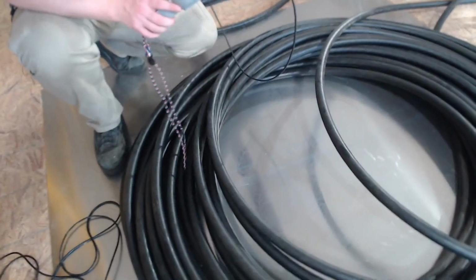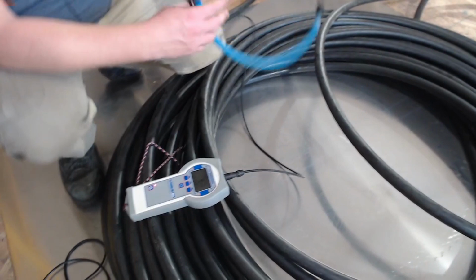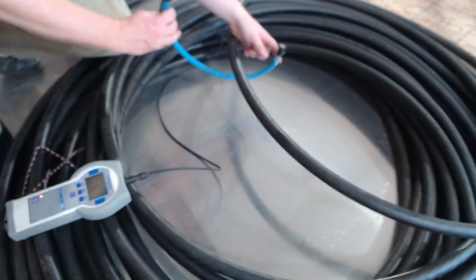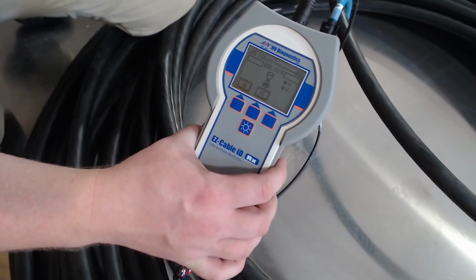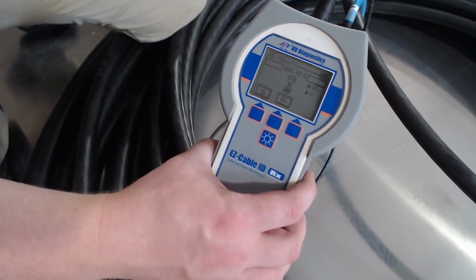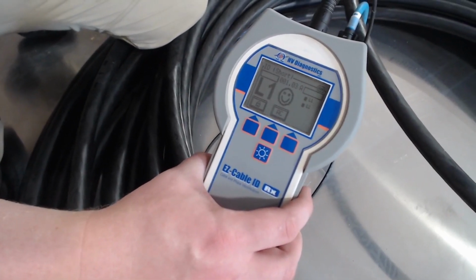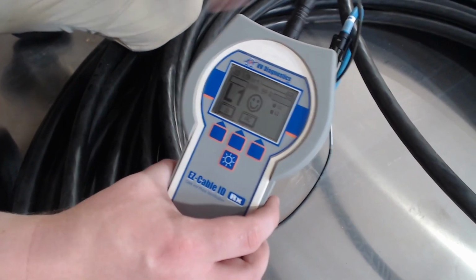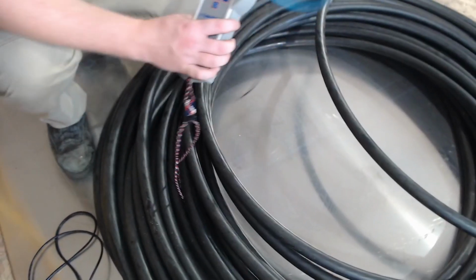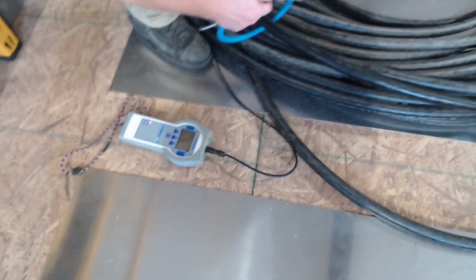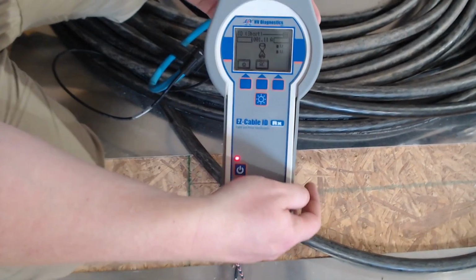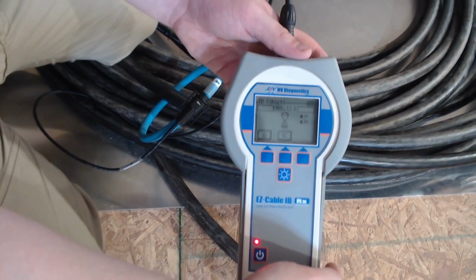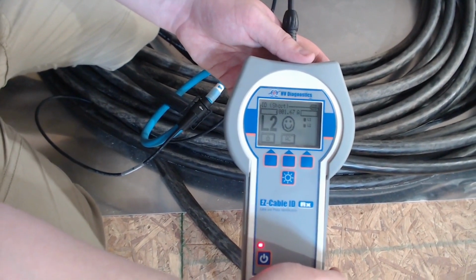All right, so now that we've verified our cables, we're going to go and ID them in the indirect mode. So we're going to put our Rogowski coil on. So, yep, it's verified for us that L1 is happy, so this is our L1 that we've induced into the shield. Moving over to our next one that we're inducing into, B phase through the shield. If I put the coil on right, it should give us another smiley face with L2. Yep, so the coil's on the right direction.